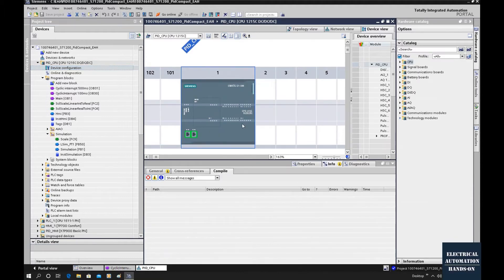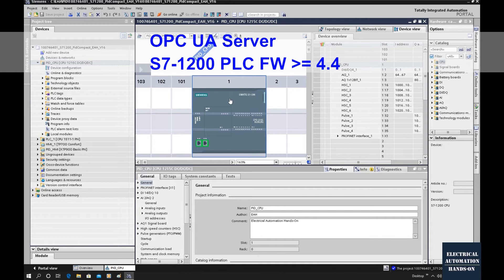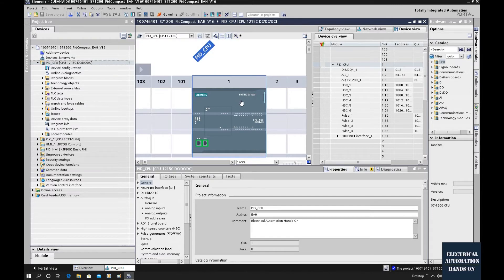The controller I'm using is a Siemens SIMATIC S7-1200 CPU 1215 controller. We need to configure and activate the OPC UA server function from this controller. Keep in mind, for the S7-1200 PLC, only firmware version 4.4 or greater supports the OPC UA server function. So we must guarantee the hardware firmware and the software configuration firmware in TIA portal are all greater than or equal to version 4.4.